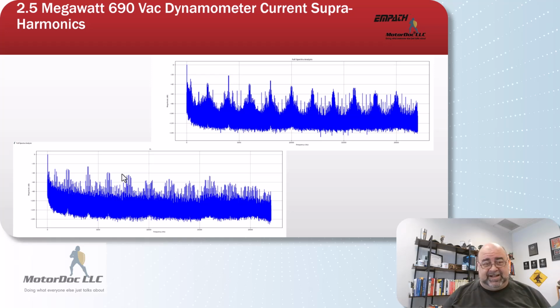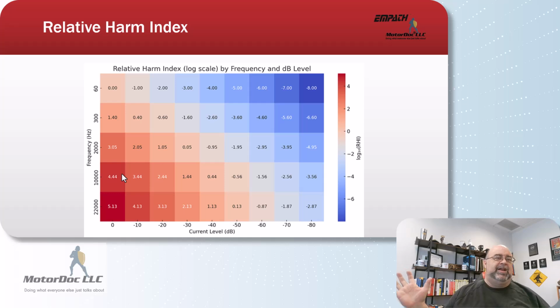It also is a fantastic antenna, and I've already done several case studies where we had cranes overhead moving along. We were picking up the cranes, and we were picking up failing LED light bulbs off the surface of the machine when doing this. So if you have a predictive maintenance tool that's using flux, I call them the flux capacitors with pixie dust, and you're trying to trend off of that, everything around it that's emitting an electric field will be picked up. And so you might get a lot more false positives, which actually seems to be the case. False positives are phenomenally great because they drive your maintenance costs through the roof because you're running around chasing non-problems. So in any case, what we came up with from all that was a relative harm index.